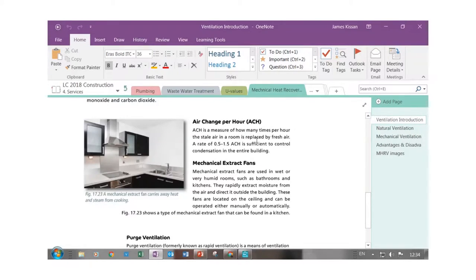For air changes, 0.5 to 1.5 air changes per hour are needed to control condensation in the entire building. That means between half and one-and-a-half times the total volume of air in a room needs to change in an hour. In this room, for example, it's happening automatically — you can see the gap under the door, so fresh air is coming in. In a non-airtight building, air escaping is replaced by fresh air coming in.